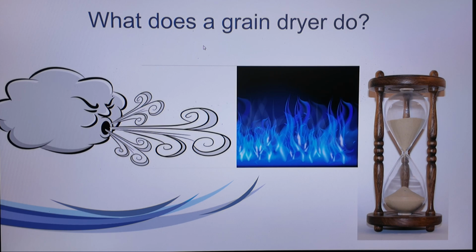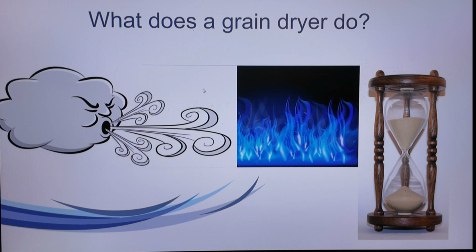That's the number one thing. The number two thing is the fan. Is it a belt drive fan? If it's a belt drive, are the belts slipping? Verify the belts are not slipping.